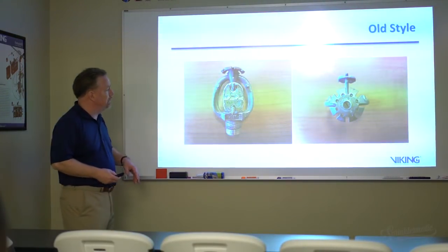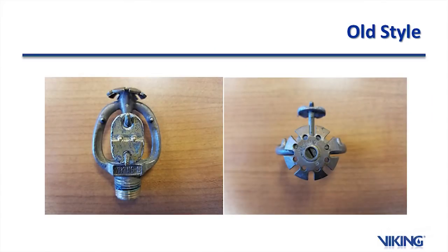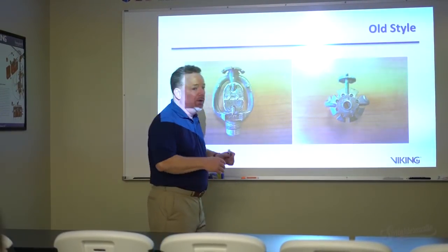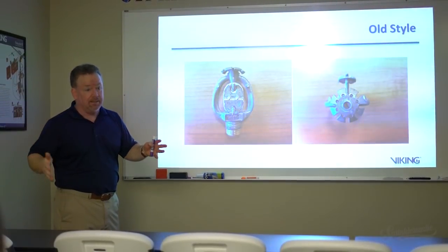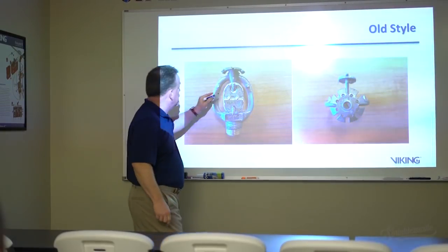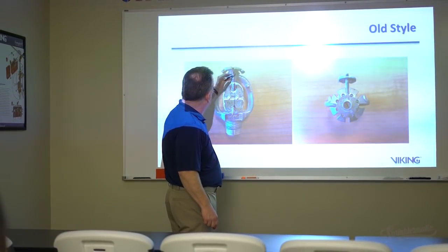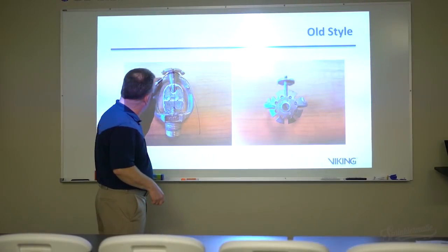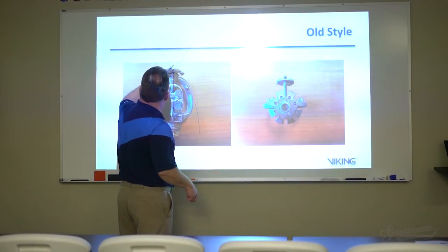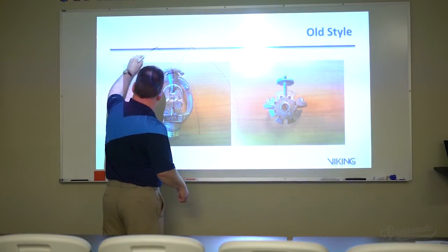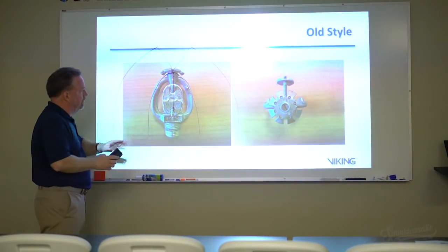Here's an example of an old style Viking sprinkler from 1942. It relied heavily on the ceiling to create its distribution pattern — about 20 percent of the water went down and the rest went up, hit the ceiling, and spread out. The problem was limited coverage, so old style sprinklers required very tight spacing to ensure total coverage.